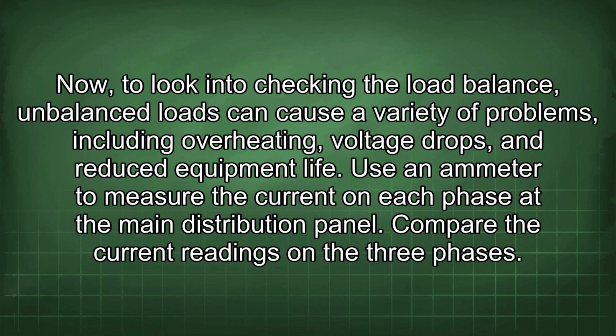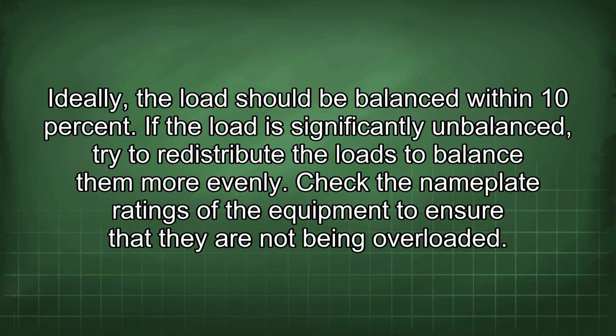Now, to look into checking the load balance. Unbalanced loads can cause a variety of problems, including overheating, voltage drops, and reduced equipment life. Use an ammeter to measure the current on each phase at the main distribution panel. Compare the current readings on the three phases. Ideally, the load should be balanced within 10%. If the load is significantly unbalanced, try to redistribute the loads to balance them more evenly. Check the nameplate ratings of the equipment to ensure that they are not being overloaded.